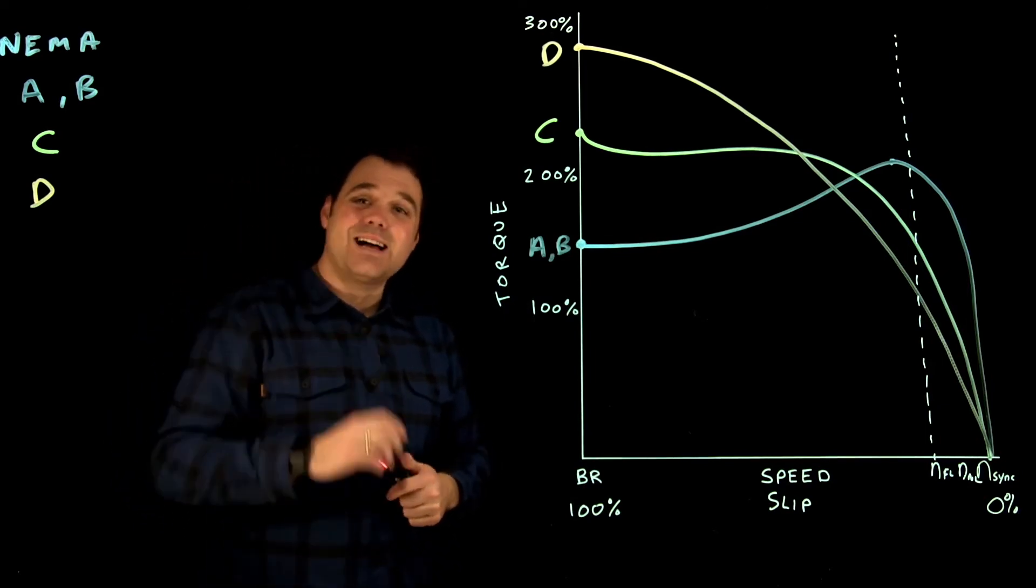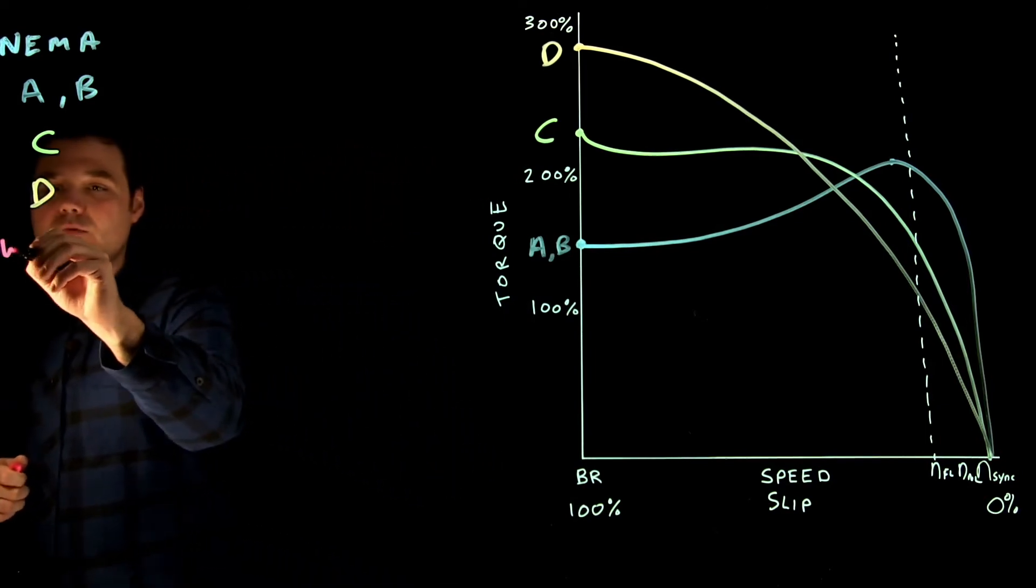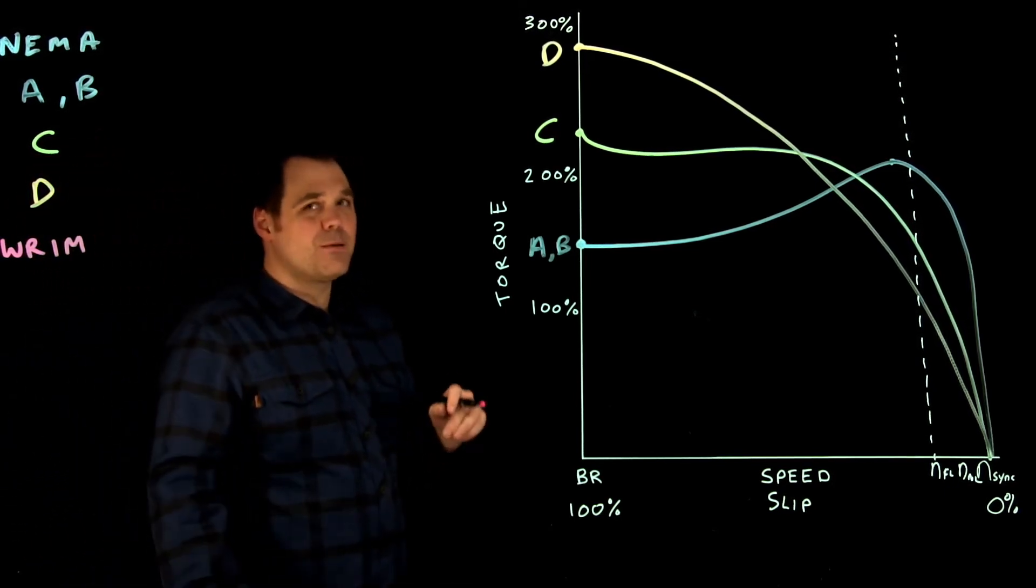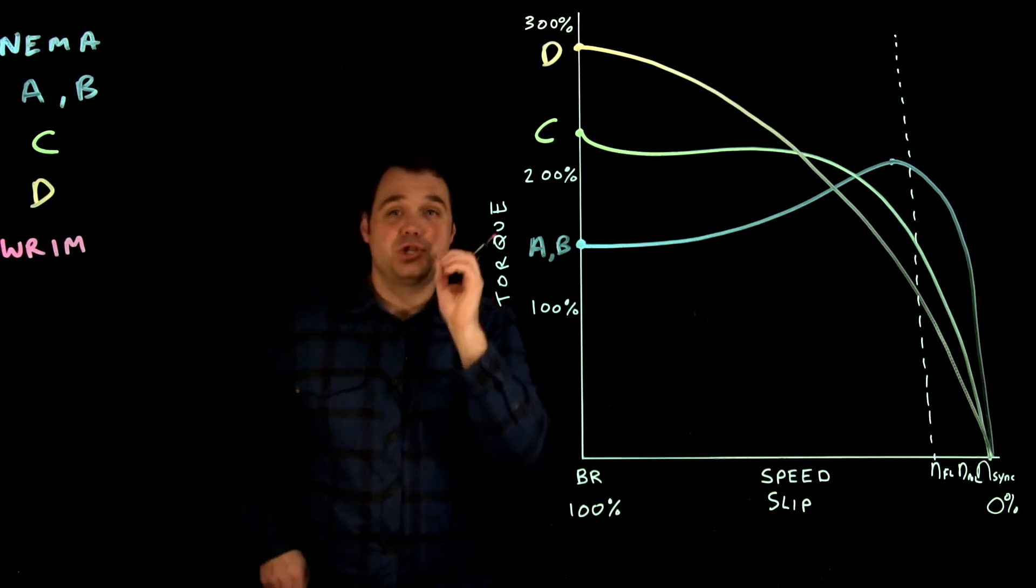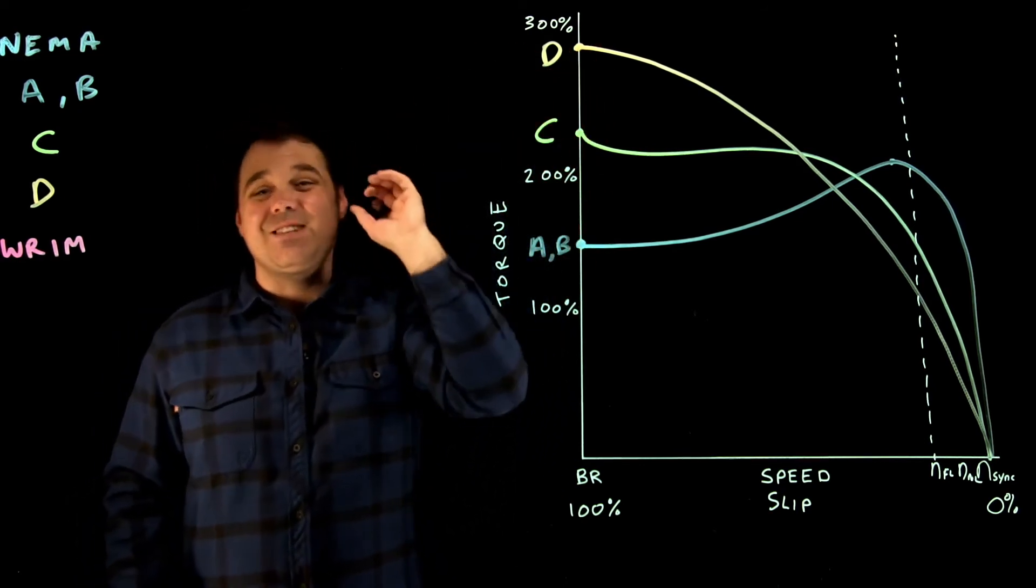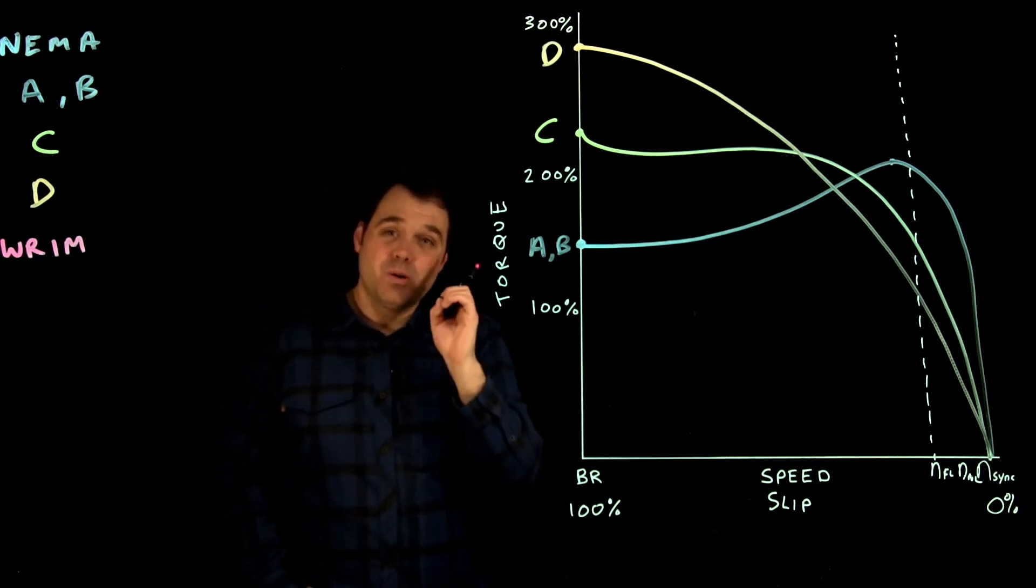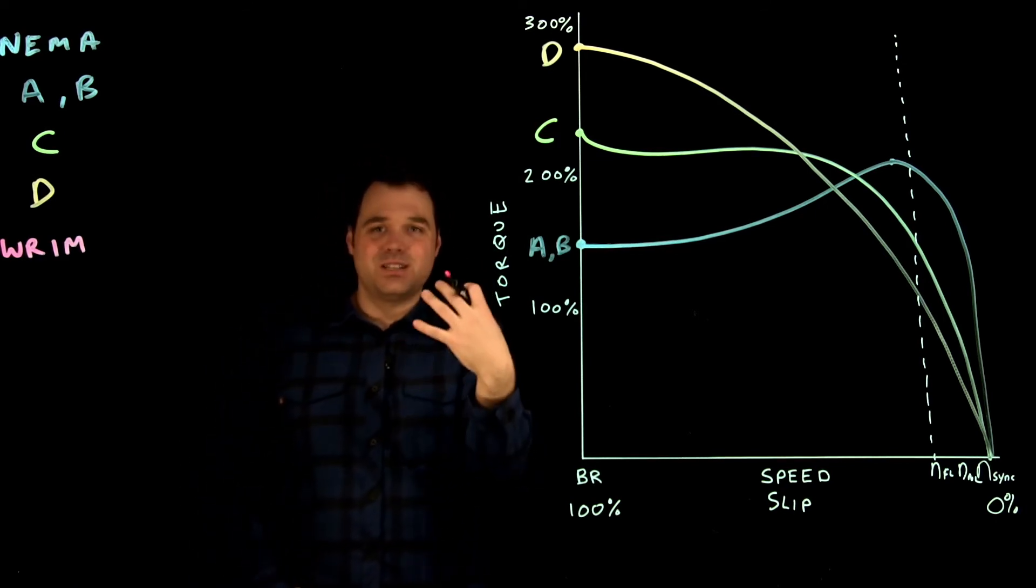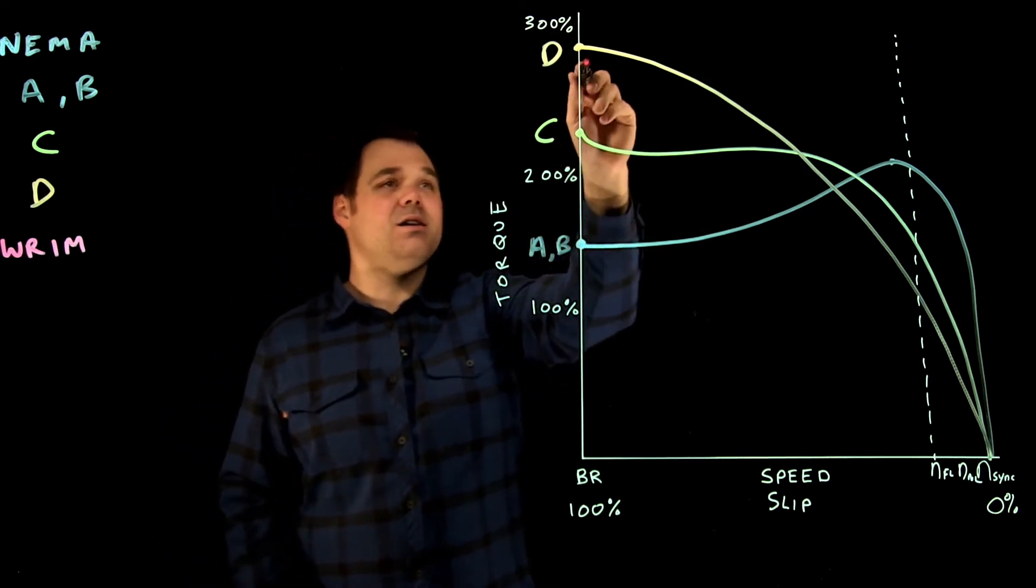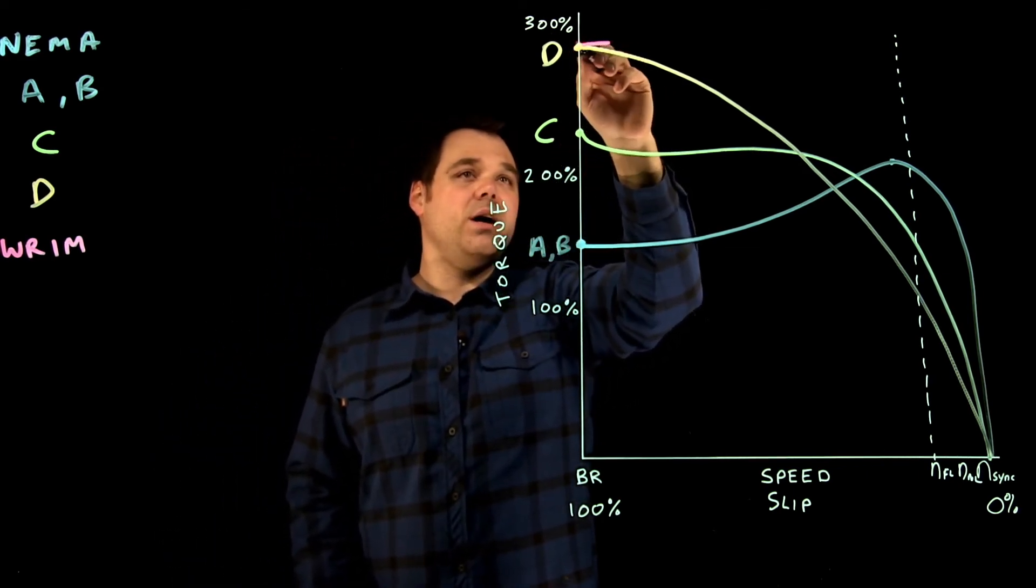But of course, the last one I want to talk about is that wound rotor induction motor rotor. The wound rotor induction motor, remember, that's the one with the adjustable resistance. So all of these rotor designs A, B, C and D have a set resistive value. With that wound rotor motor, we're adjusting the resistance, which gives me the room to play. So I can keep my torque really high.